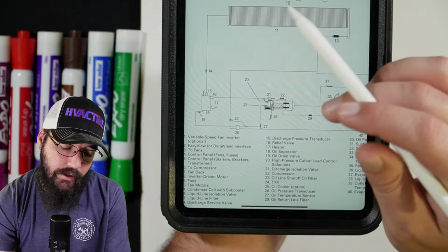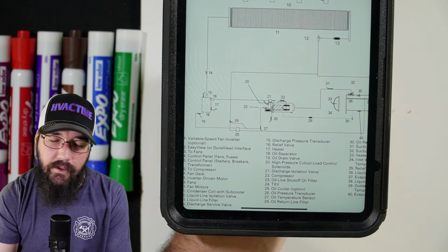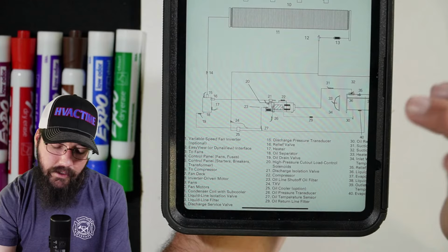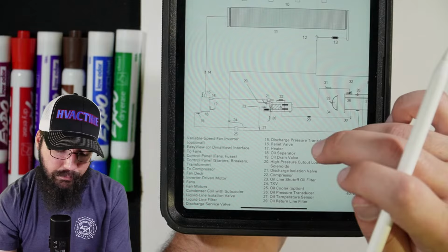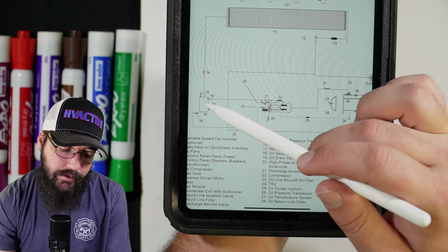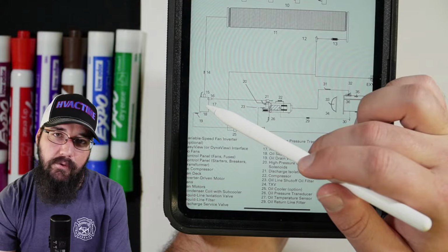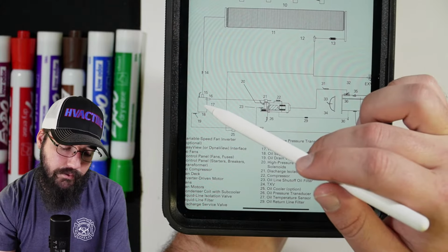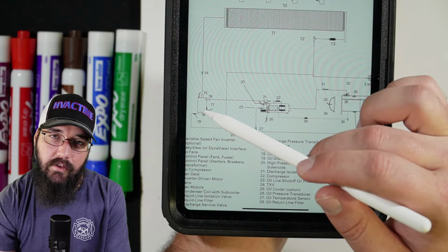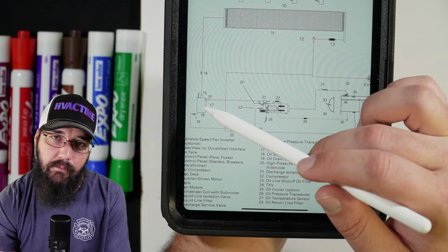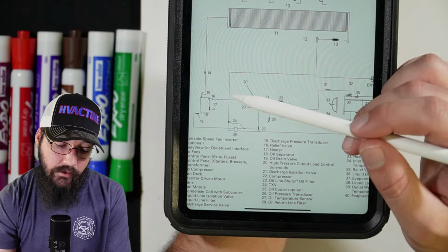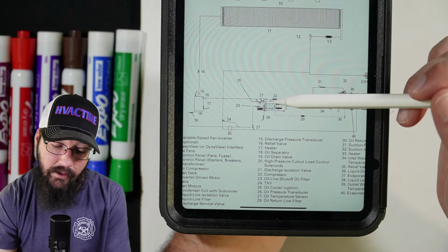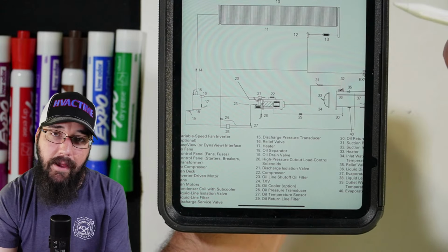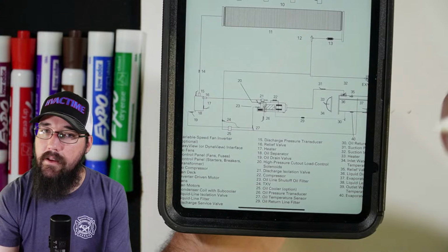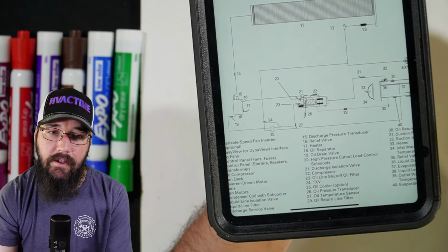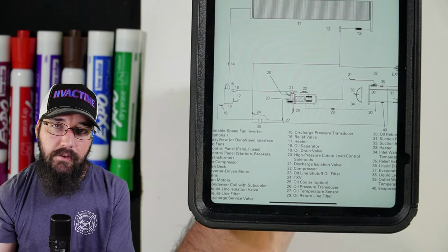If we truly put it in the separator, and this is where it just gets really tricky, there's not always a perfect answer. If we put that refrigerant in and start stacking liquid refrigerant in our separator, that liquid refrigerant will stack in the bottom of our separator and it'll sink below the oil. So then when we go to turn the compressor on, what are we feeding? Not oil. We're feeding refrigerant right back into our compressor, right? Same issues we have with any circuit. Bearings don't need refrigerant, they need oil.